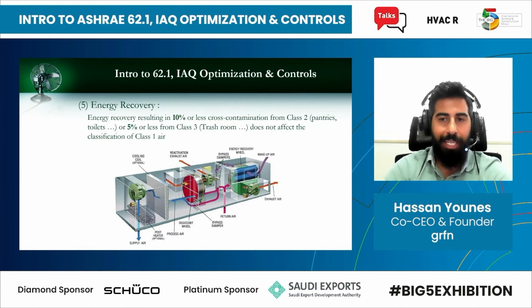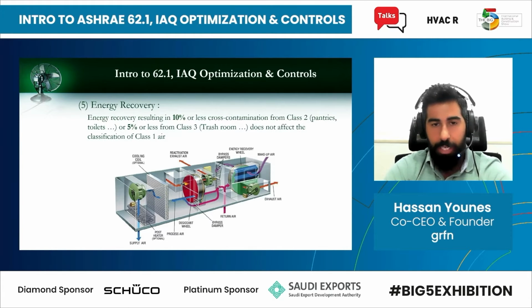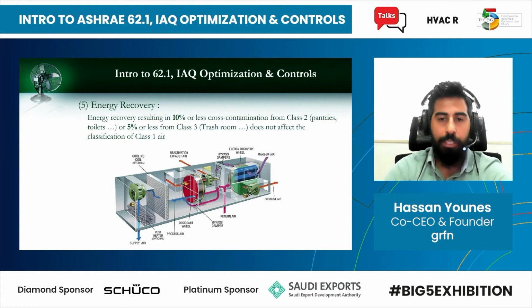So if you have, let's say, class 2 exhaust, then 10% of that can go into the outside air, the fresh air, and that is fine as per the standard. If it's class 3, then 5% is the maximum that can be transferred. And again, it should be non-intentional transfer, so it's cross-contamination happening, because these wheels or these energy recovery devices do have cross-contamination. You cannot use class 4 air for heat recovery, because you're not allowed to mix any of that with the outside air.